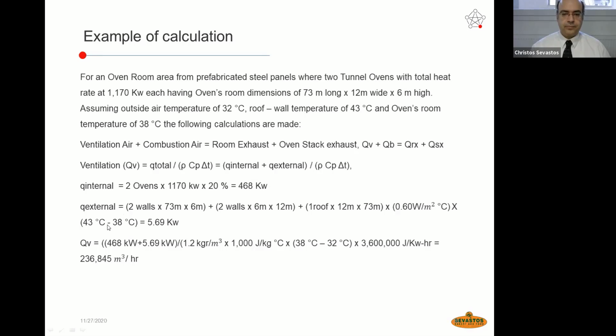temperature inside the oven. If we combine those 2 together, 468 kilowatt is the Q internal heat from the oven, as we have calculated here, plus the external heat coming from the roof and walls, divided by the density of air, by the specific heat of air, and of course the difference between oven room temperature and outside temperature: 38 oven room temperature minus 32 degrees, the outside temperature. This is the conversion factor from joule to kilowatt hour, and this equals 236,800, 237,000 let's say, cubic meter per hour.